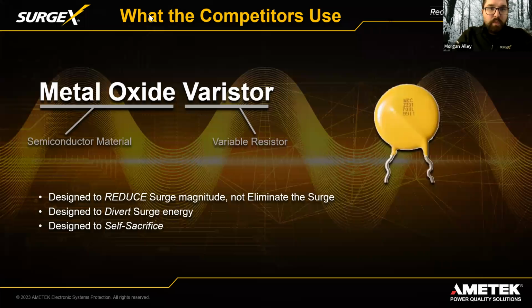To dive into what the rest of the market is doing: these MOVs wear out, and as more surges are diverted, the lifespan is reduced until it completely fails. How many surges an MOV can take varies depending on how intensive the surge is or how cheaply it's been manufactured. On average, an MOV costs 5 to 10 cents to manufacture. These have been around since the late 60s and haven't been innovated upon much—extremely outdated technology.